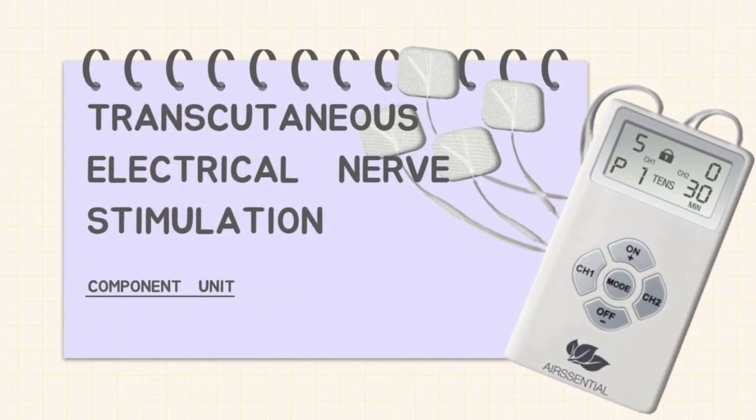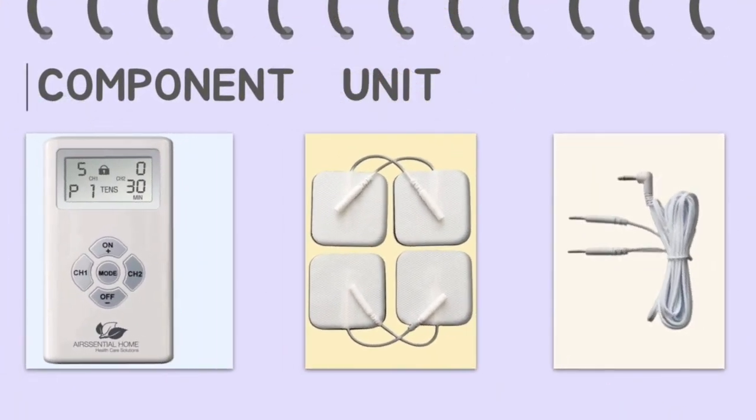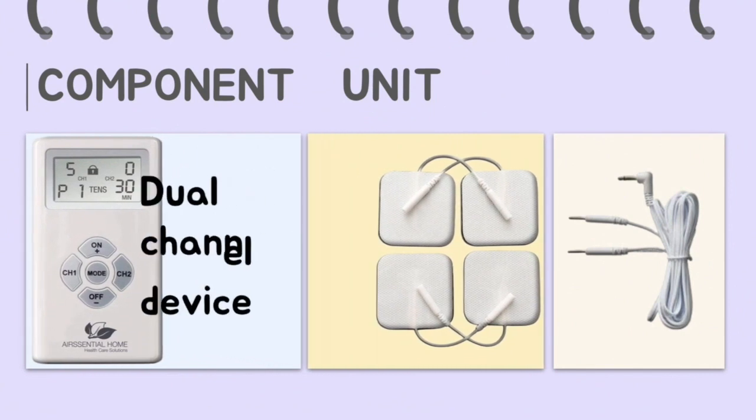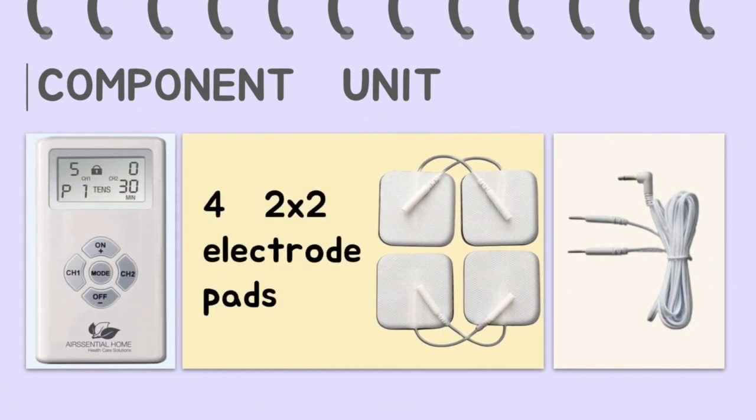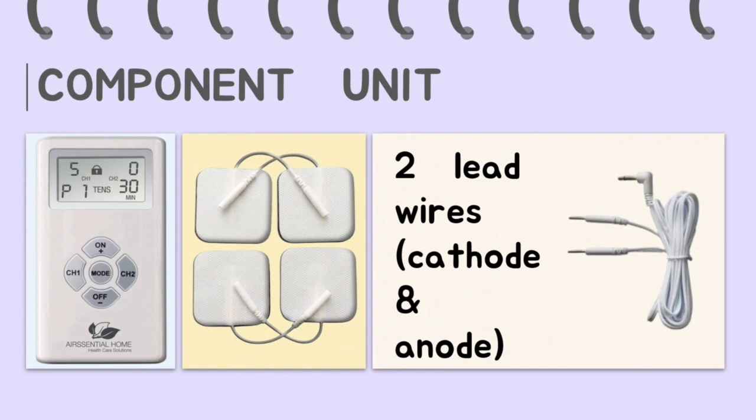Introducing transcutaneous electrical nerve stimulation. TENS consists of three things which are dual channel device, four, two times two electrode pads, and lastly, two lead wires cathode and anode.